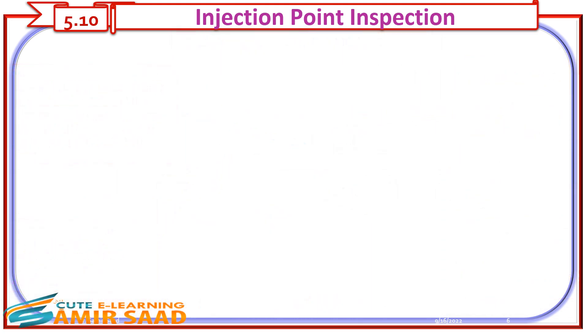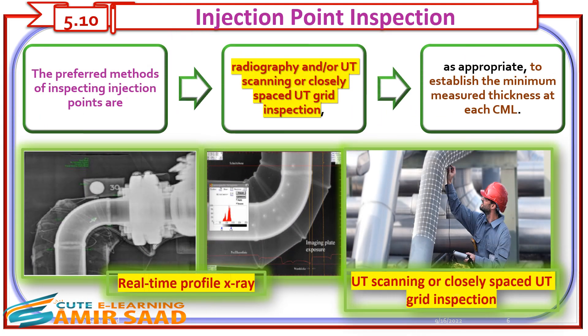The preferred methods of inspecting Injection Points are radiography and/or UT scanning or closely spaced UT grid inspection, as appropriate, to establish the minimum measured thickness at each CML. Close-grid ultrasonic measurements or scanning may be used, as long as temperatures are appropriate.